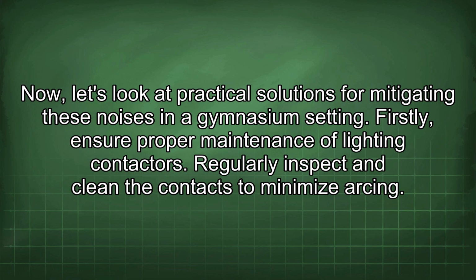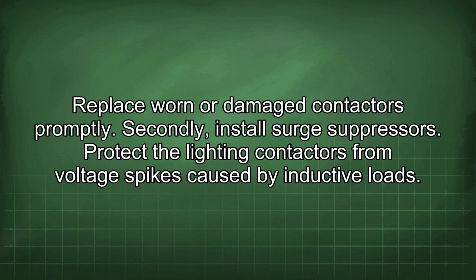Now, let's look at practical solutions for mitigating these noises in a gymnasium setting. Firstly, ensure proper maintenance of lighting contactors. Regularly inspect and clean the contacts to minimize arcing. Replace worn or damaged contactors promptly. Secondly, install surge suppressors. Protect the lighting contactors from voltage spikes caused by inductive loads.